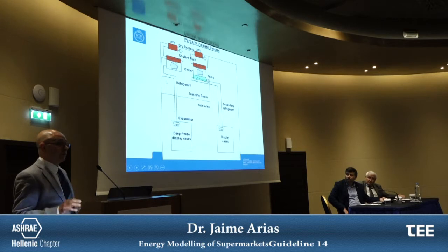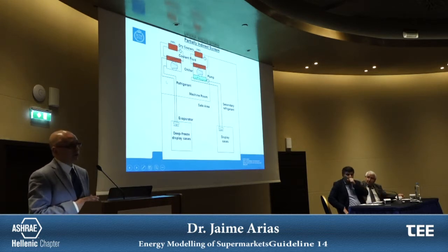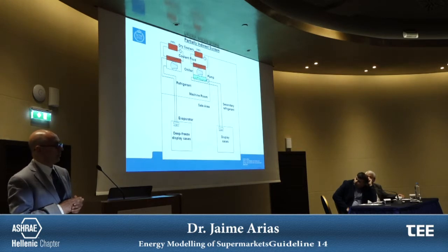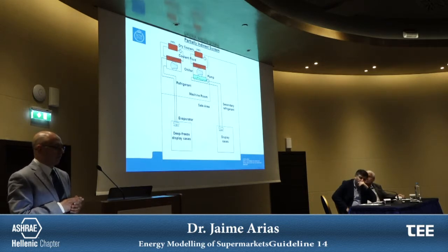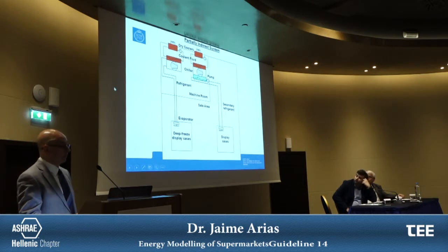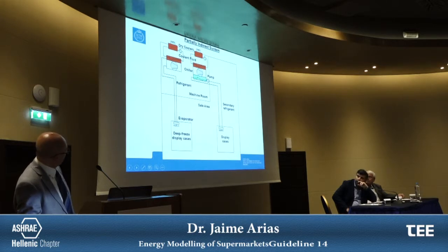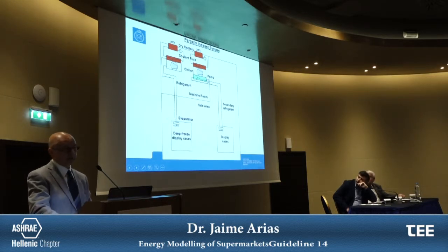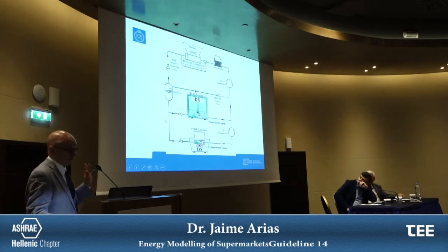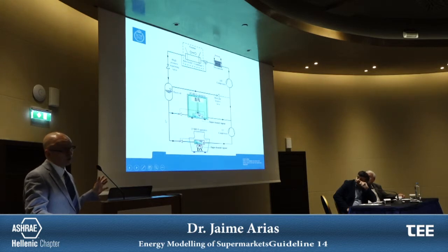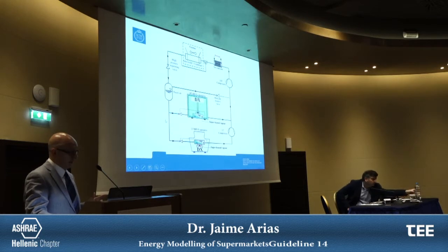In the low temperature level, it was difficult to find secondary refrigerants because we are talking about around -30 degrees. It's difficult to find because of the high density and the viscosity. So this was the main problem. And also, fluids working at this temperature have problems with corrosion. So the idea is that in the low temperature level, in many of the supermarkets, we use refrigerant, that means direct expansion, and we use, well, an indirect system on the condenser side. Well, as I mentioned before, this is the new system we install in many supermarkets, the booster system. So all the new supermarkets are moving to CO2 systems. So this is the normal system today, at least in Sweden.